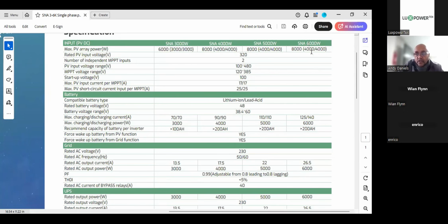The max charging, so we're going to look here under the column for the 6 kilowatt. The max charging is 125 amps. Max discharging is 140 amps. So if we work on 52 volts times 140, that's going to give us 7.2 kilowatts. Now, 7.2 kilowatts obviously exceeds the capacity of the battery, but we could have 140 amps at 48 volts or 46 volts. So that's why we have these capacities here. The max charging and discharging power is 6 kilowatts.